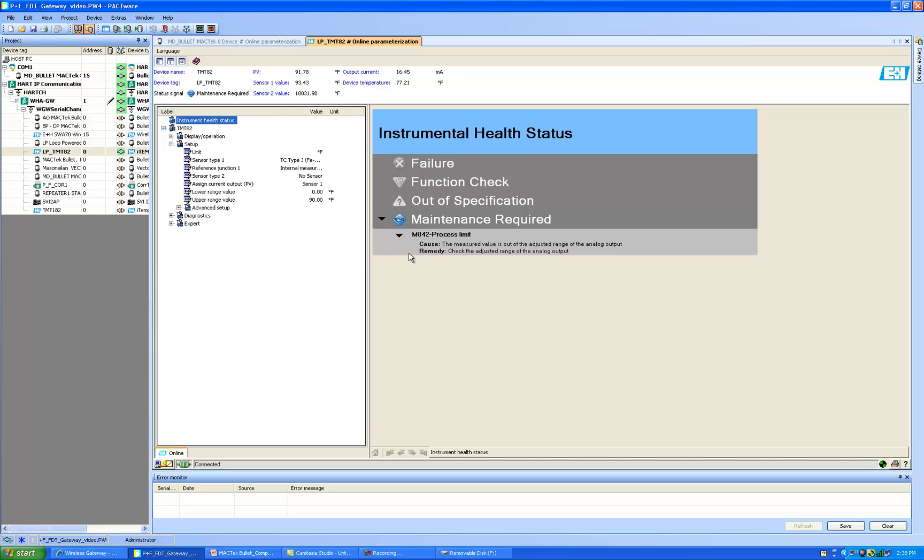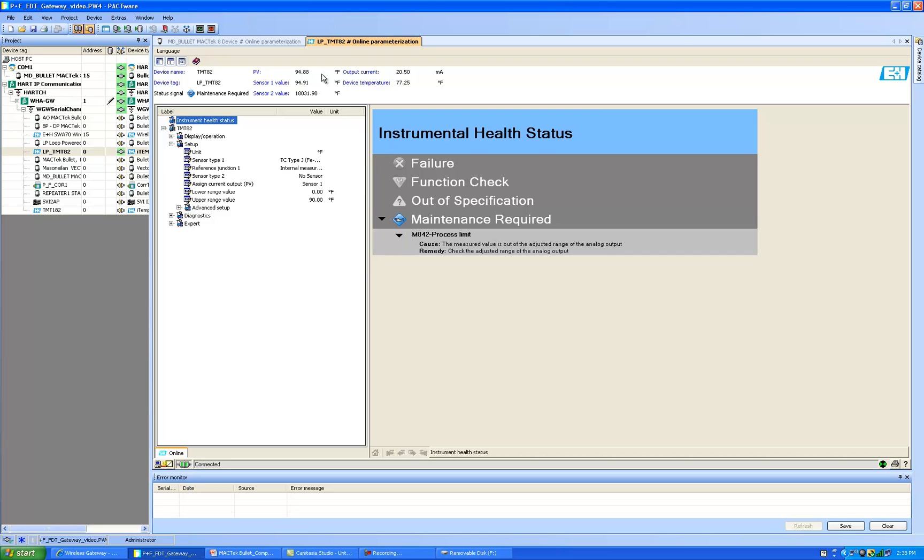If you can read this fine print it says the cause is the measured value is out of the adjusted range of the analog output. If you look at my setup screen right here I have the upper range value set at 90 degrees. With me holding the thermocouple we're up over 91.78 and that shows a quick failure. This will show an open thermocouple, a device malfunction, internal temperature out of spec, many diagnostic features which is what makes wireless HART so attractive for condition monitoring, data acquisition and just having a program to check the health of your instrument 24-7.